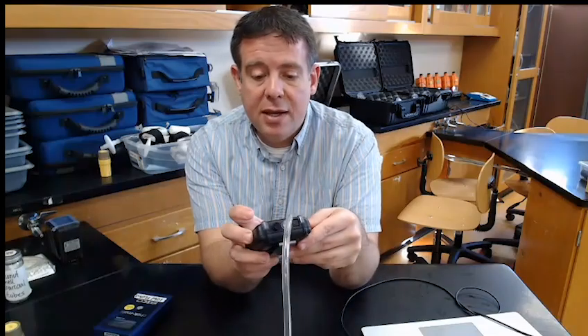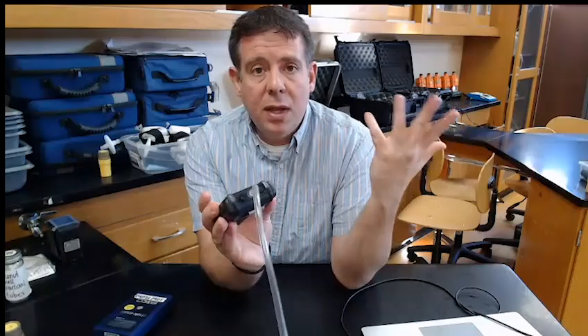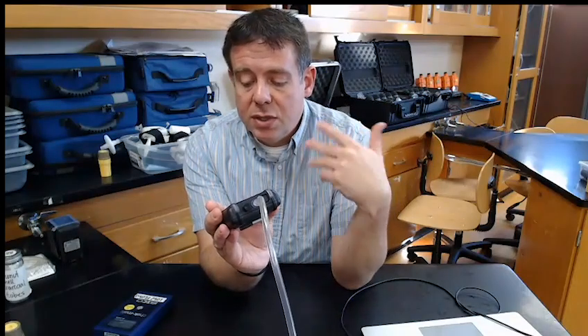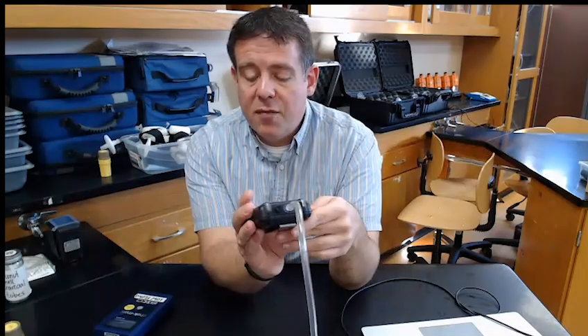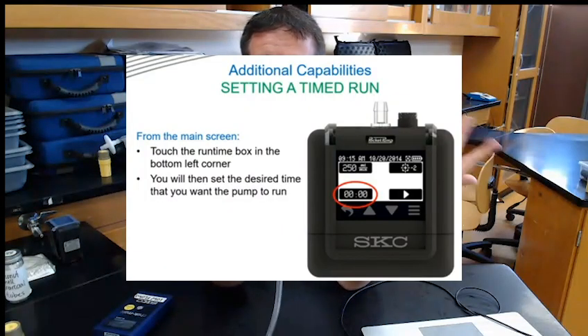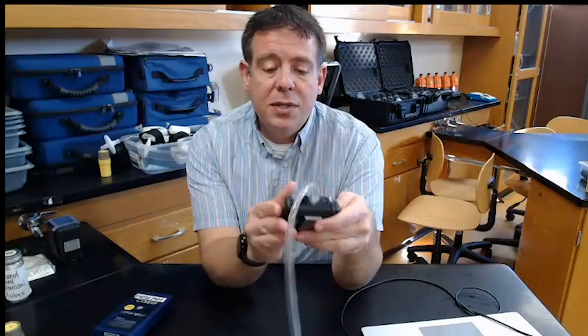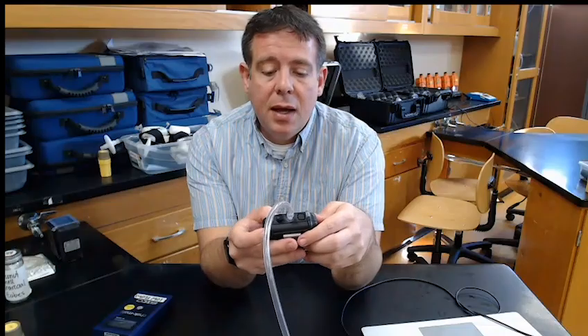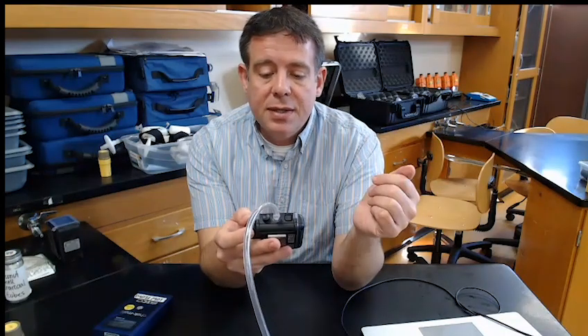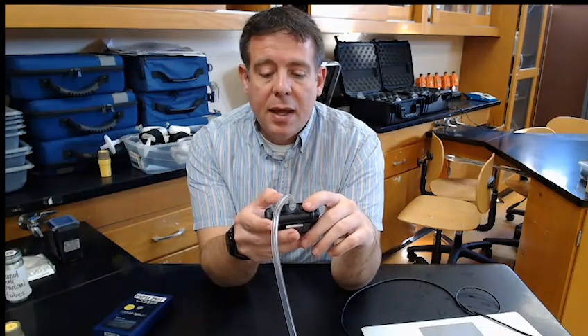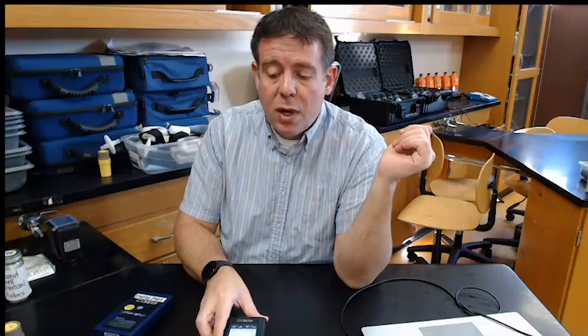So we had that calibrated in here. And so then when we go to sample, we have our calibration. We'll do a new sorbent tube and use that for a sample. So if we were going to sample with a new person after this calibration, we hit that time duration, typically 8 hours, but a lot of times with sorbent tubes we're using multiple tubes, so maybe just 2 hours. It gives it in minutes, the first one in hours, and we'll just set it for 2 hours, so 120 minutes, and I'll go back, and then we'll hit that play button, and it will start sampling for us. So when we're done, we'll do a post calibration with the new sample, and just record what it gives us. And so we'll compare that.